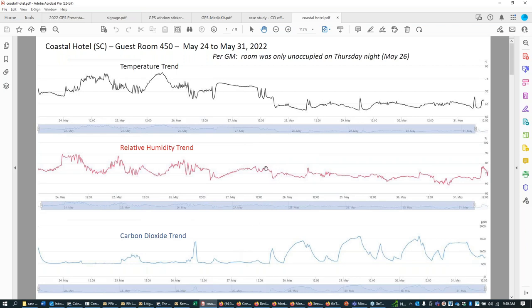Just incidentally, this hotel had a very serious negative pressurization problem. It did not have appropriate makeup air, outside air being conditioned. It had restroom exhaust throughout the property that was causing a net negative pressure, and it was just pulling in lots of unconditioned air and humidity into the building. I've helped them with that, and that's a project that is queued up to actually fix that. But as a result, you can imagine if you've been in a hotel that's got humidity control problems, you know that there are typically odors associated with that, and they definitely had that.